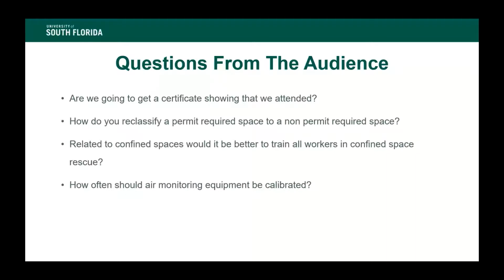Our next question, how often should air monitoring equipment be calibrated? I'll take that one. You have to calibrate according to manufacturer specifications. Read the equipment manual and see what the manufacturer is recommending. In general, you have to also consider the conditions in which you're using your air monitoring equipment. I would recommend that you calibrate every time you're going to use the equipment. If you're going to do confined space entry tomorrow, make sure that you calibrate before you do that.